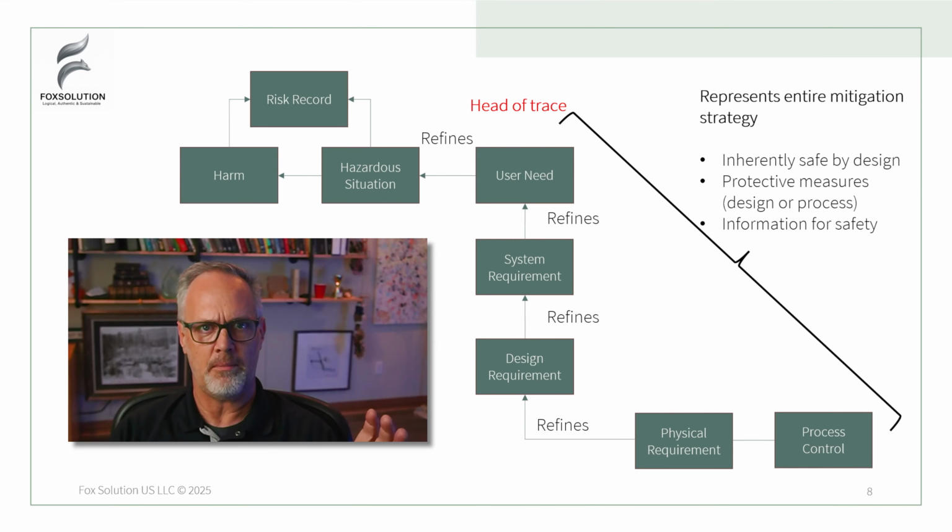And so one of the problems that you have when you're making these definitions is dependent upon what the harm outcome of that hazardous situation is, we might have a different occurrence rate that's associated with it. So now each one of the hazardous situations has what's called a P1 factor. This is based on the 14971 risk management protocol, the appendix in that document. The P1 factor is how often that hazardous situation occurs. And that's carried inside the hazardous situation. This is the only thing really that we can adjust to mitigate the risk in our system. So we have a pre-mitigation P1 and a post-mitigation P1.